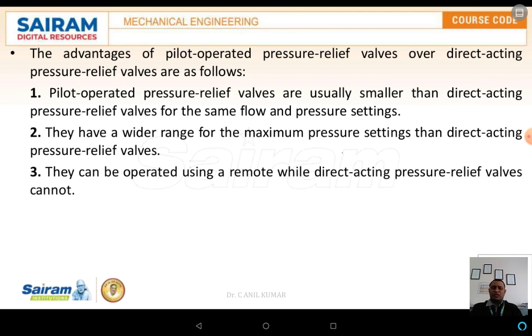The advantages of pilot-operated pressure relief valves over direct relief valves are: large or maximum pressures can be operated very easily; there are two different types of valves — the pilot relief valve and the main relief valve — so safety is maximized; the component is simpler compared to a simple relief valve; they have a wider range of maximum pressure settings than direct-acting pressure relief valves; and they can operate using remote control, while direct-acting pressure relief valves cannot.